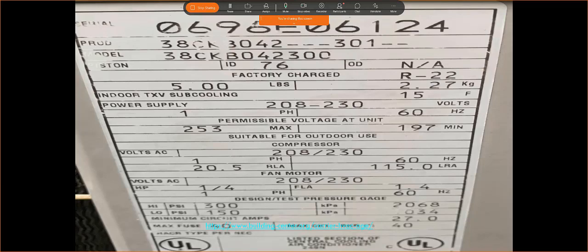What ends up happening is, if our line is extremely long, we may need to add refrigerant. So there are different tests that we do to verify that, but we at least know from a starting perspective, this unit came with 5 pounds of refrigerant. If I were to have a different type of metering device, a TXV, it would be set at 15 degrees. So this is stuff you guys will know by the end of the course.